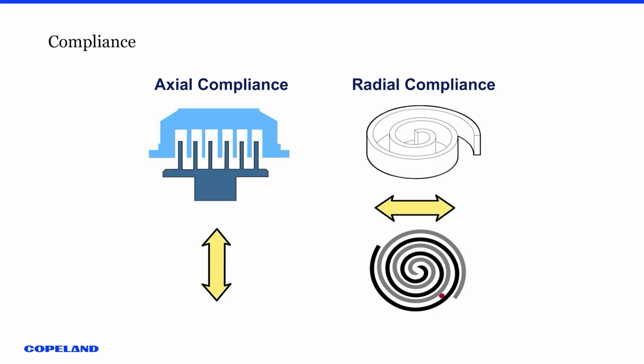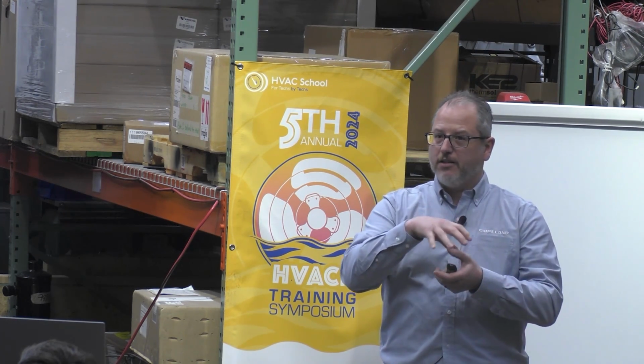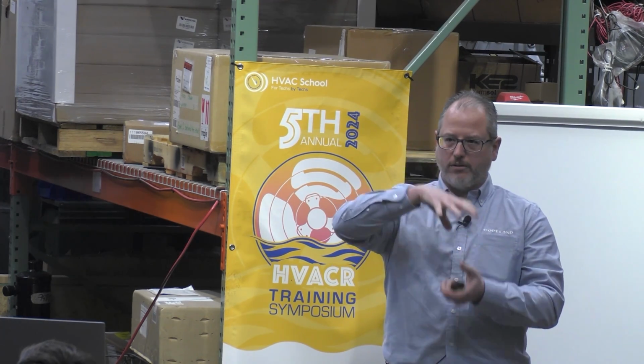Our scroll compressors have compliance, so the axial lifts it up that 1 millimeter, and then we have the radial. So if we have any little droplets of liquid or debris, like that little red dot there, usually centrifugal force is what's keeping our scrolls together. It will separate a little bit. So it'll lift up axially and radially, and that stuff will just go right through.